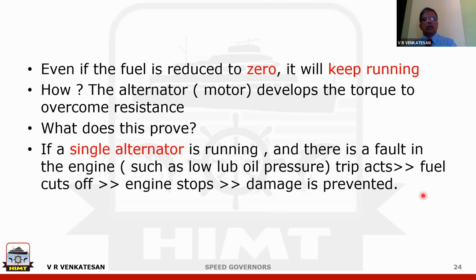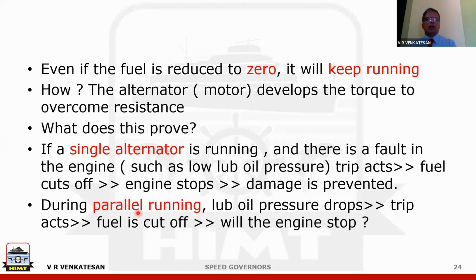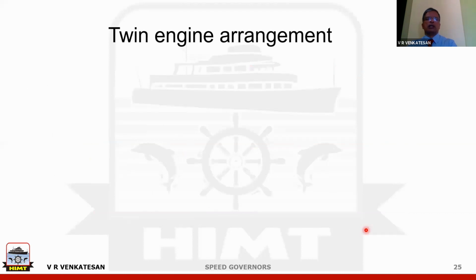Now, if the same problem happens in parallel running. In the parallel running condition, the lube oil pressure drops. Why does the lube oil pressure drop? Because of a clogged filter or because there is no oil in your sump. Then the trip will act, fuel will be cut off, but will the engine stop? No, sir. It will not stop because the alternator will keep driving it. So what is necessary for us is that you must disconnect.